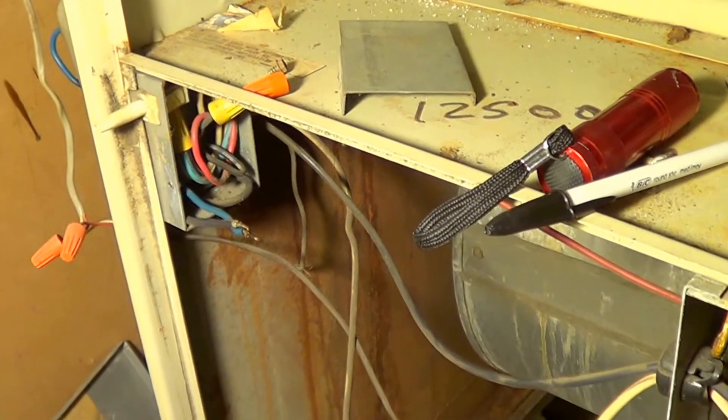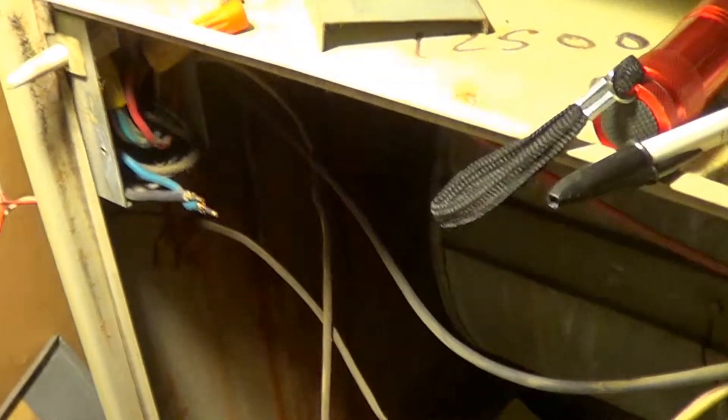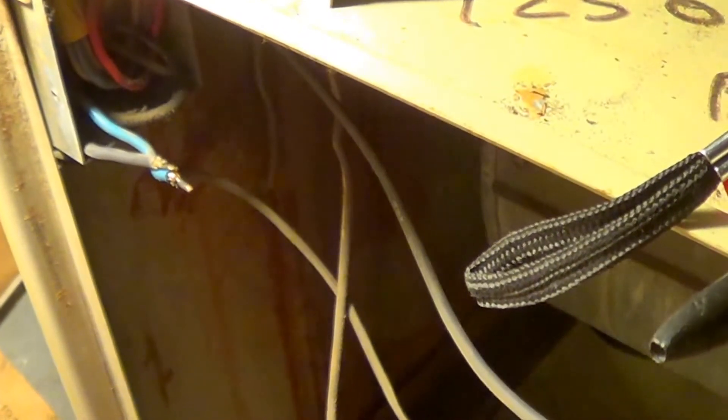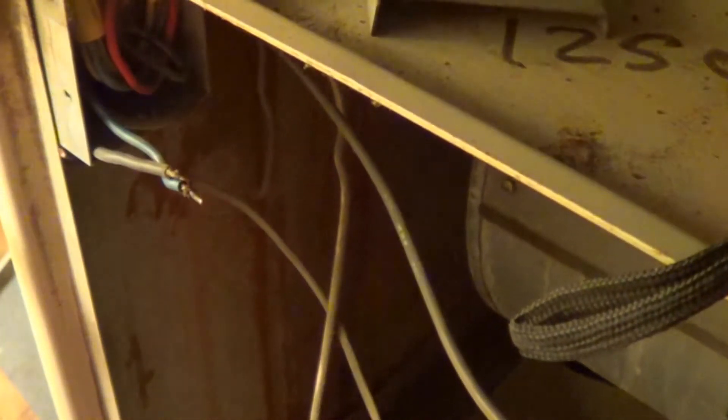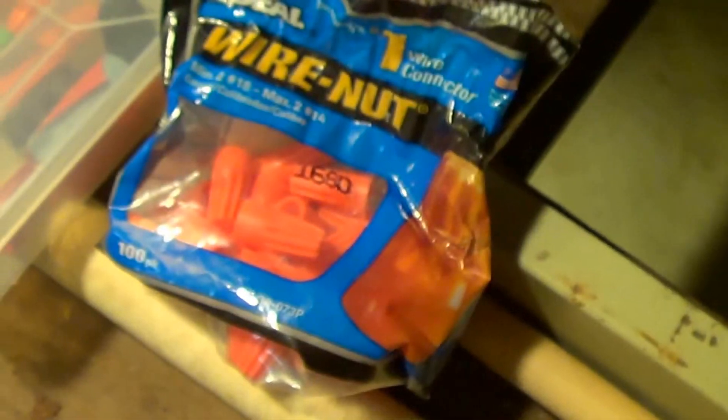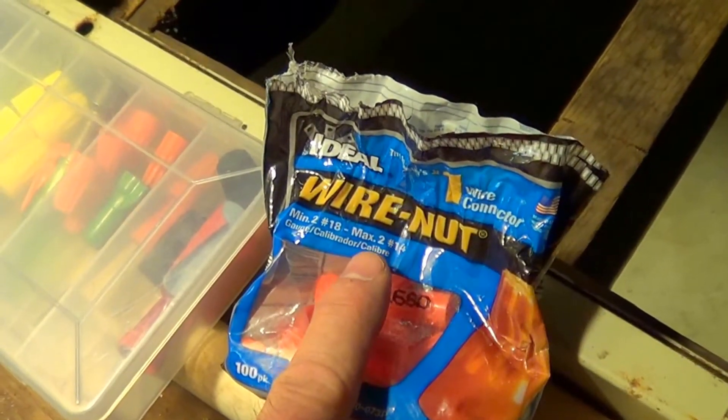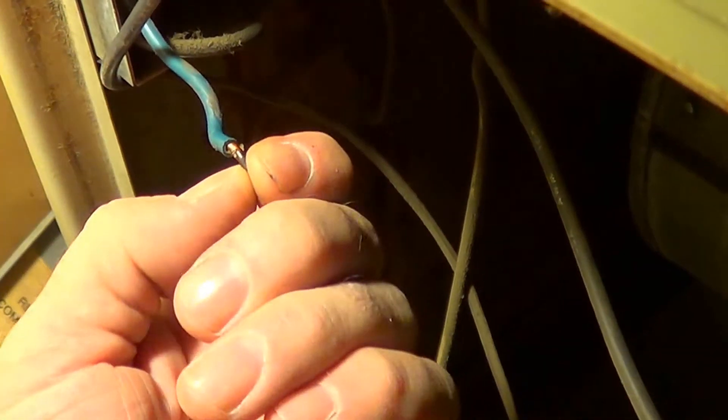Got a right furnace, left furnace, and this other one was dead. Because these are twinned together, nothing was going on. It just basically stopped. I've got to clean this up and put a wire nut on there. Never had this happen before on this unit, but it was strange that this connection decided to go bad right on a cold day. Here's my collection of wire nuts. What's interesting is the orange one says a max of two number 14s. Over here they had a number 12 wire and this is about an 18.